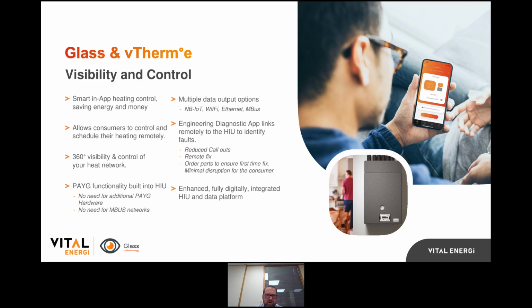The HIU can also report on network faults and any particular issues that might be occurring at that point in the installation. So the operator has the ability to identify issues and, in most cases, manage those remotely. Our engineers can also access the HIU remotely, so they can identify any particular faults or issues occurring in that particular appliance. This means that should they need to attend site to repair or make a fix to that equipment, they can go there with full knowledge of the issue, with all the parts in place, which means that any service visit is resolved first time. So it reduces the disruption to the consumer and to the operator, but it also enhances the lifespan of the unit.